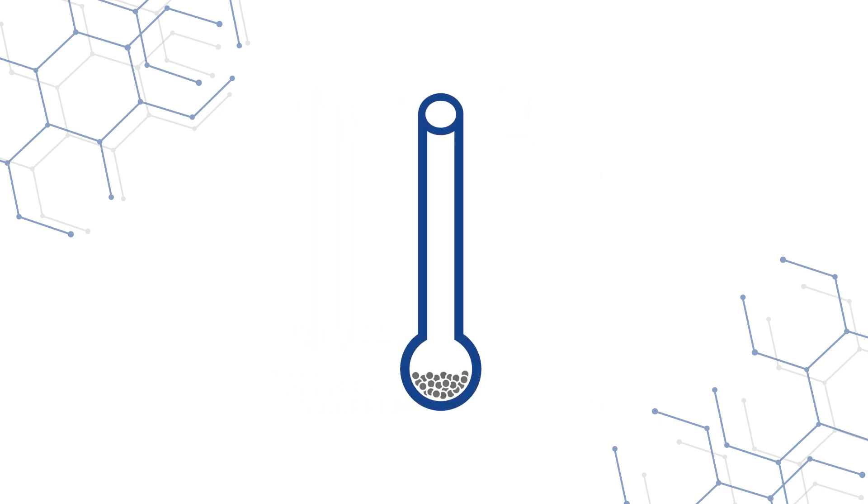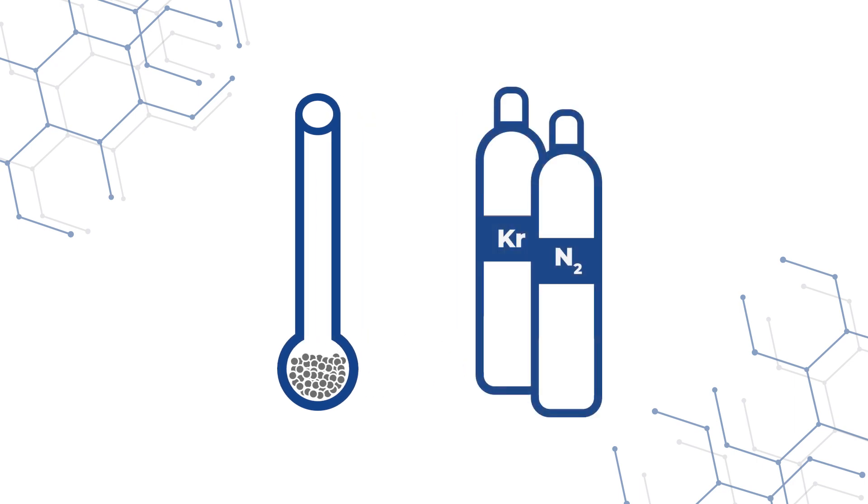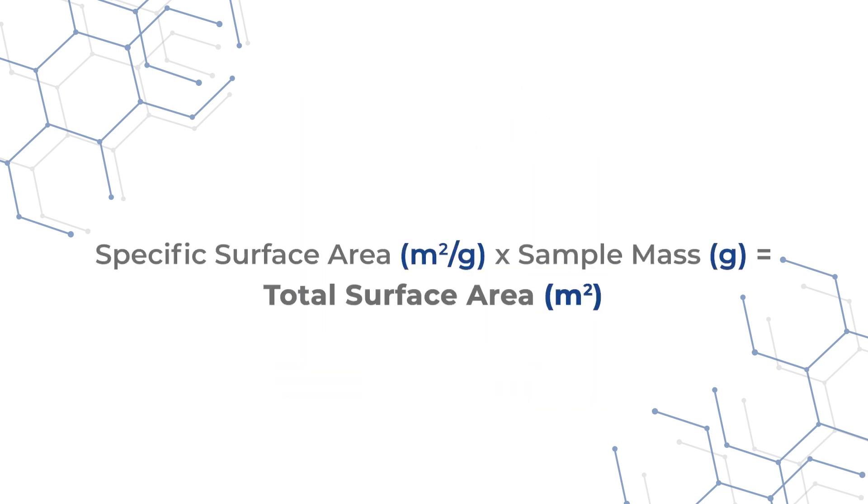First, how much sample is available. This helps to determine which adsorptive gas can be used based on how much total surface area is available. The total surface area is calculated by multiplying the specific surface area by the sample mass.